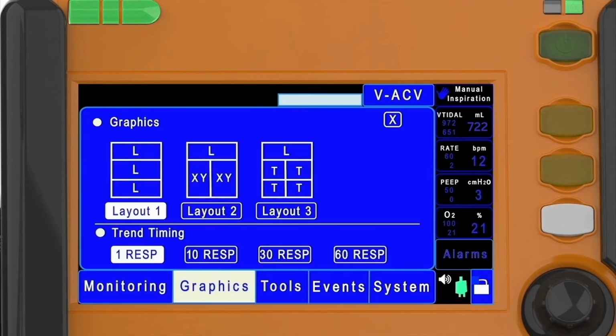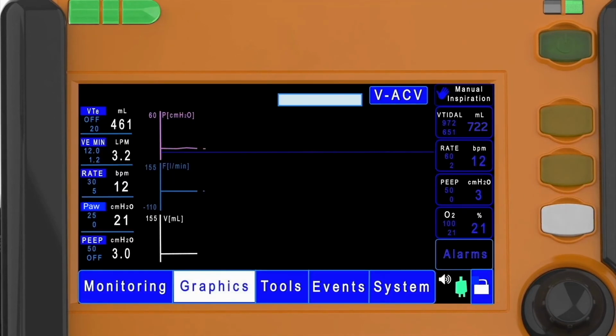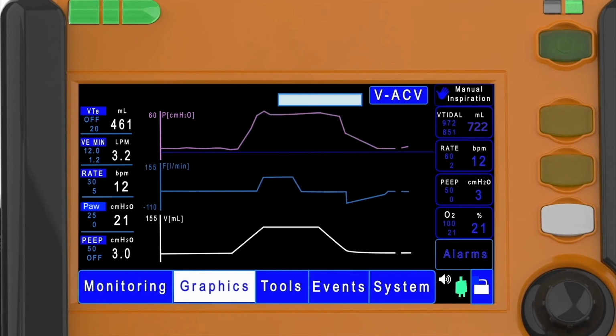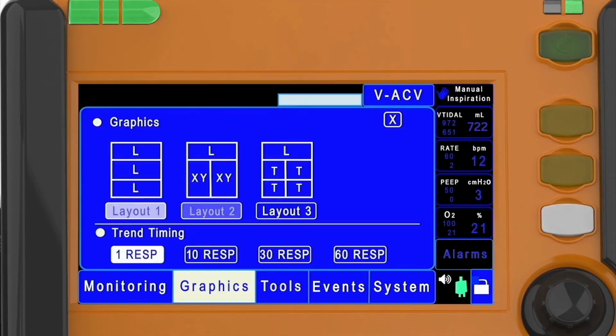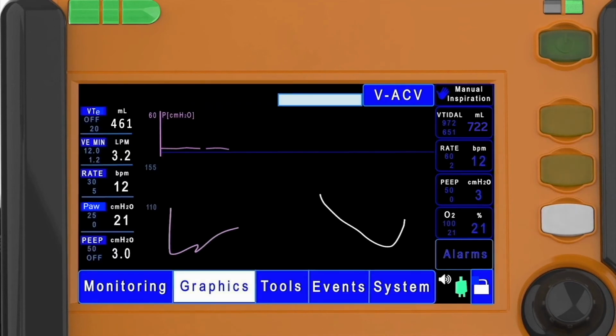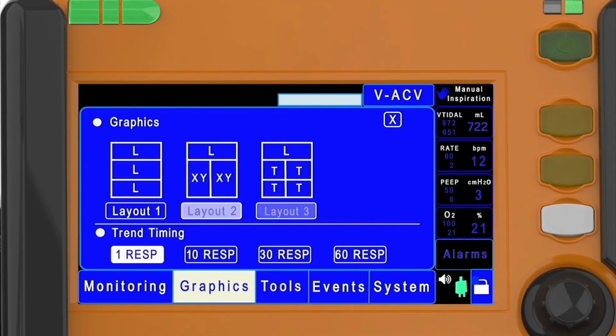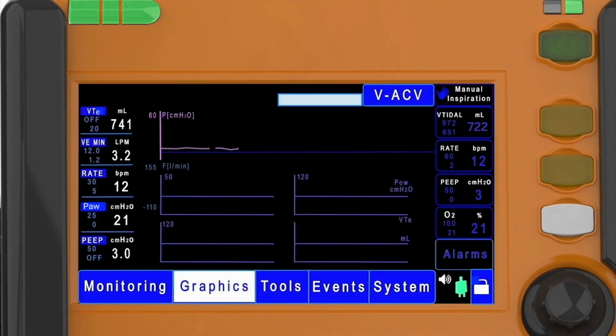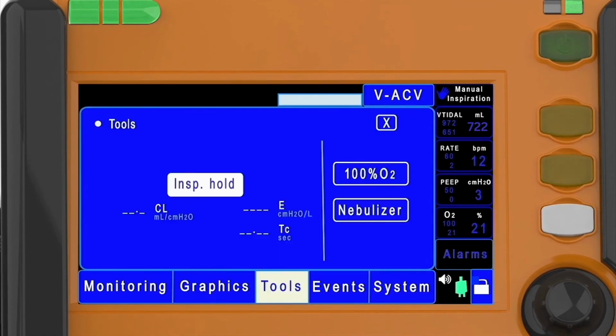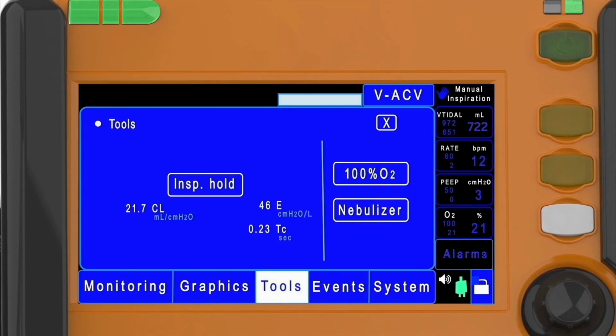You can also change the graphics settings by selecting the preferred layouts. Layout 1 showcases all three waveforms, that is pressure versus time, flow versus time and volume versus time. Layout 2 showcases a waveform with two spirometry loops. Layout 3 showcases the trends of the last 72 hours. When you hold the inspiratory hold button, you can measure all the three parameters. Please note that this ventilator could be upgraded to nebulizer as well.